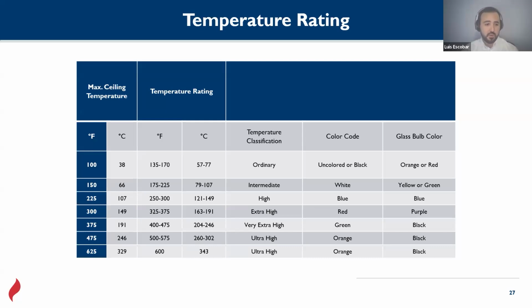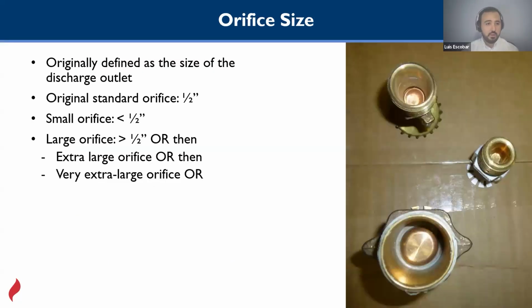Personally, I've never used purple or black. These are applications that I've never worked on, but I've used the blue because I was designing a plant that had a process that was releasing a lot of heat, and they needed this temperature. Orifice size, this will be the orifice size of water discharge. The most common one a lot of years ago was the 1/2 inch, but now we have even orifices smaller than this for residential occupancies. For offices, for example, it is 1/2 inch. For storage it is 1 inch or 3/4.